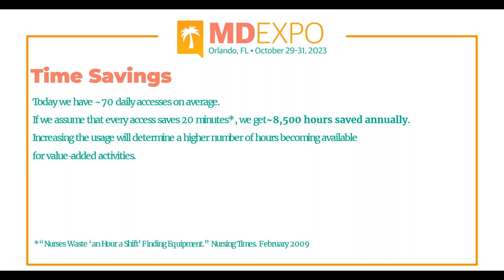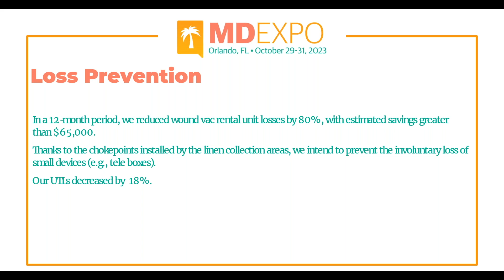In terms of loss prevention, we are monitoring what we are able to prevent from being lost in terms of teleboxes and glucometers. We did reduce our wound vac rental losses by 80%. And there's a dollar value there, so we compare before RTLS and after RTLS. Now we're tagging every wound vac that enters the facility, so that when it's time to return it to the owner, we are able to find it. So that was a huge success. And also our UILs, unable to locate or could not locate, decreased by 18% on our end for PMs.